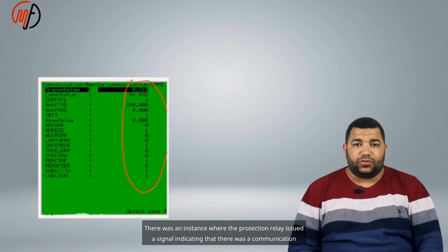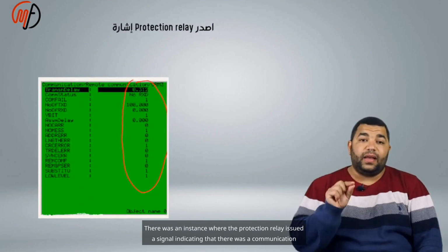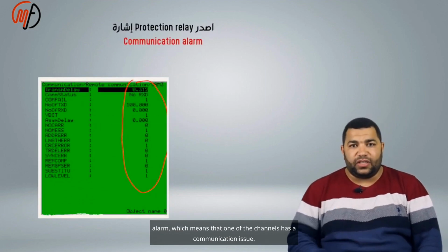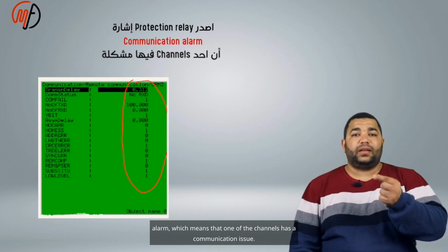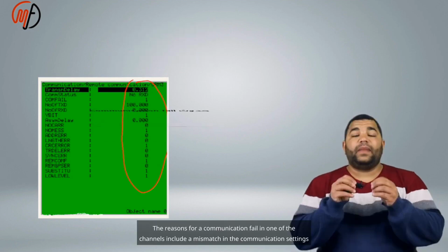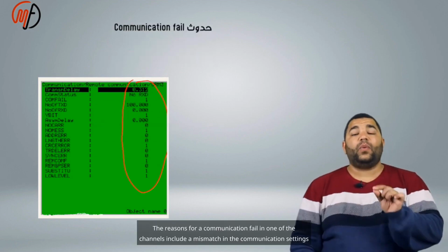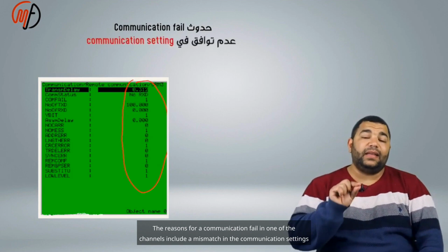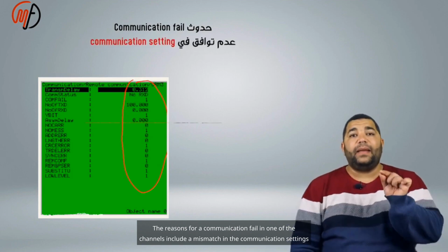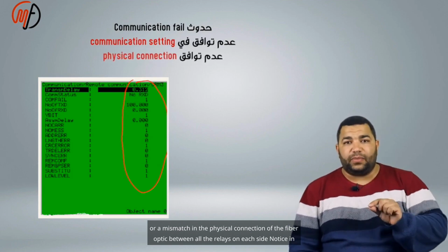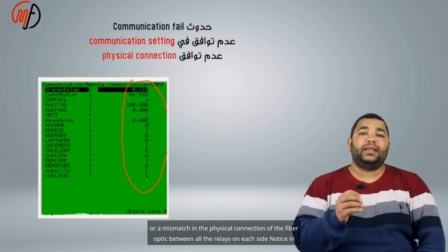There was an instance where the protection relay issued a signal indicating a communication alarm, which means that one of the channels has a communication issue. The reasons for a communication fail in one of the channels include a mismatch in the communication settings or a mismatch in the physical connection of the fiber optic between all the relays on each side.